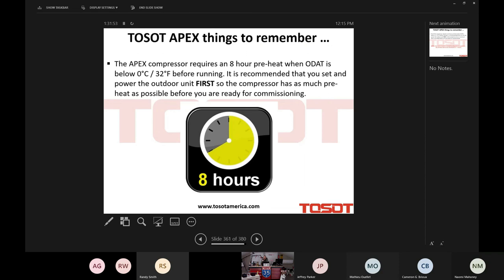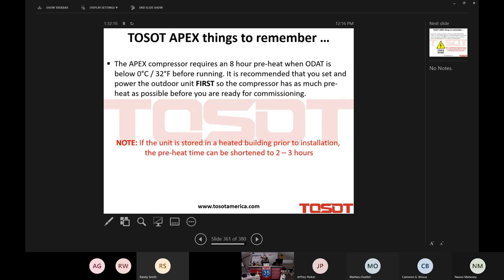Another thing to remember, listen now, if the outdoor temperature is below 0 degrees Celsius or 32 degrees Fahrenheit, did you hear me now? I'm going to say it again. If the outdoor temperature is below 0 degrees Celsius or 32 degrees Fahrenheit, before running that system, we need to preheat the compressor for 8 hours, all right? Now, having said that, if the unit is stored in a heated building, like your warehouse, I know your warehouse probably isn't heated, but it's not outdoors, right? Yeah, I mean, no, you do have human beings working there, so I'm sure it's 62 degrees, even if it's 58 degrees Fahrenheit, that's what I'm talking about. You can shorten that preheat time to 2 to 3 hours.